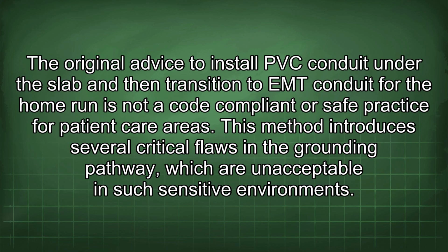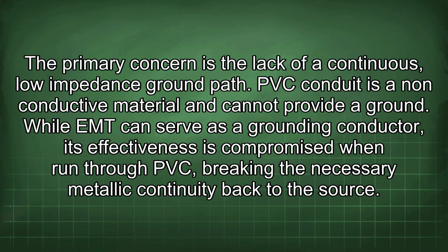The original advice to install PVC conduit under the slab and then transition to EMT conduit for the home run is not a code-compliant or safe practice for patient care areas. This method introduces several critical flaws in the grounding pathway which are unacceptable in such sensitive environments. The primary concern is the lack of a continuous, low-impedance ground path. PVC conduit is a non-conductive material and cannot provide a ground. While EMT can serve as a grounding conductor, its effectiveness is compromised when run through PVC, breaking the necessary metallic continuity back to the source.